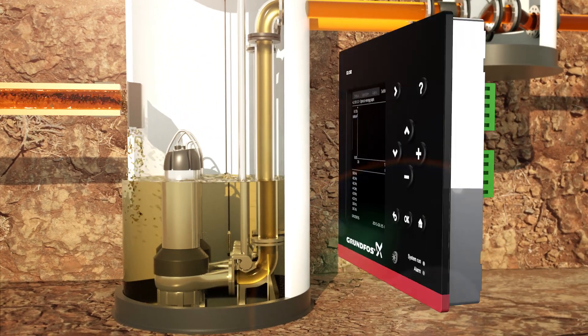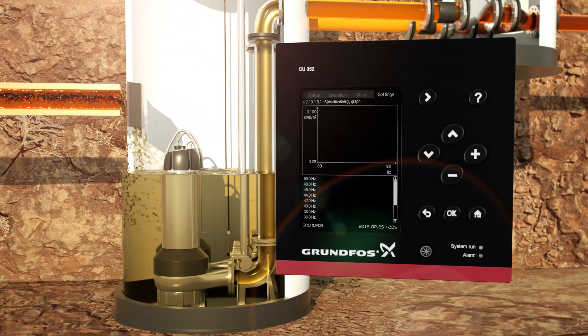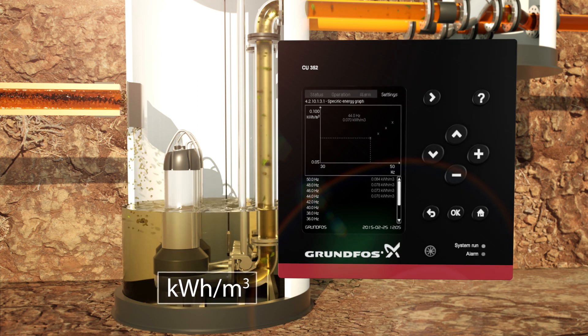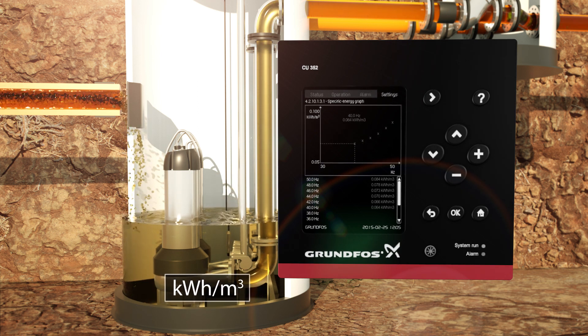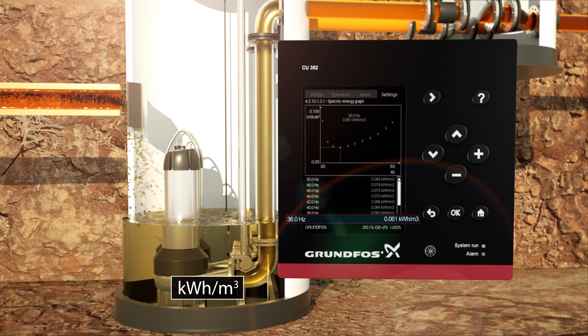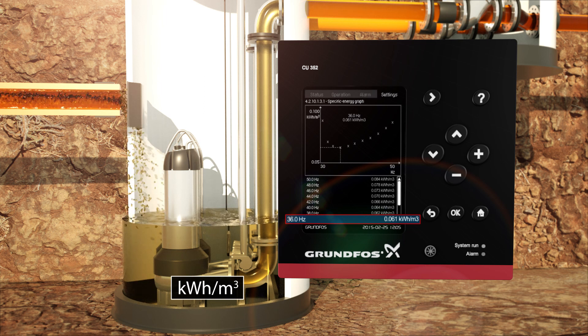Controls continuously learn and adapt to duty conditions in the specific pumping system. The controller immediately adapts pump speed in response to data from the frequency drive and a flow meter. Energy optimization is done based on everyday tests in which optimum frequencies are calculated. This gives a continuous overview of pumping efficiency.